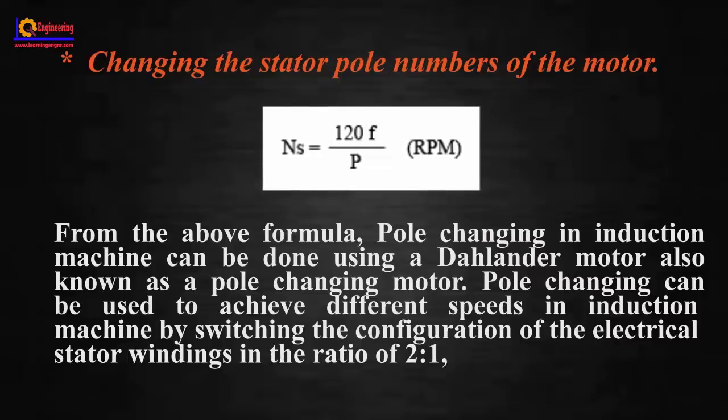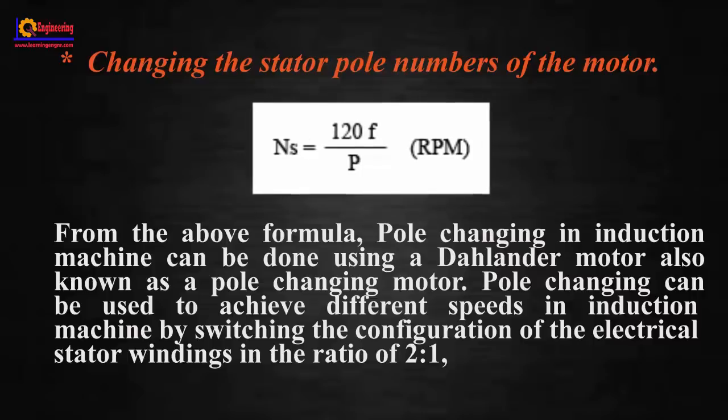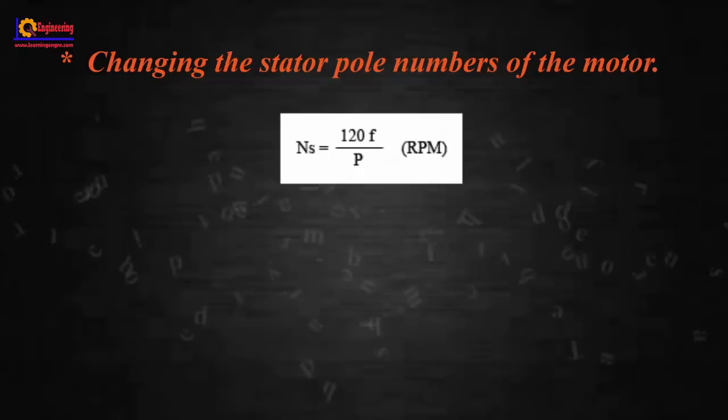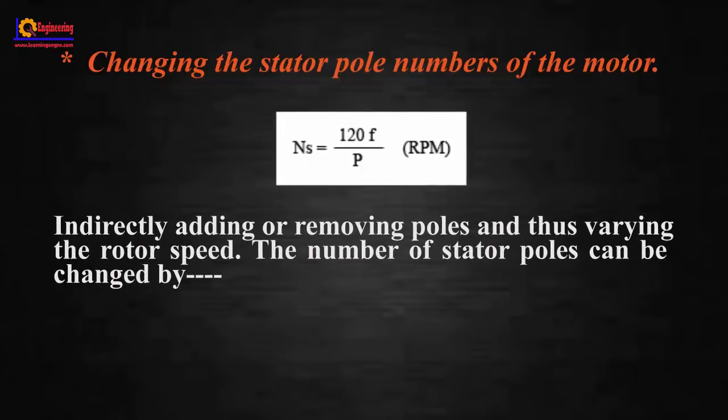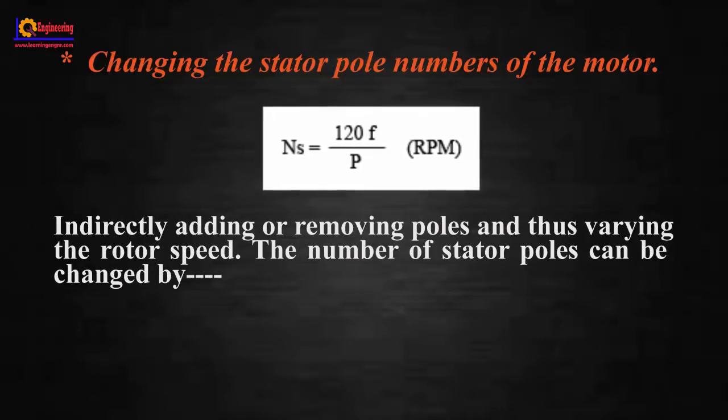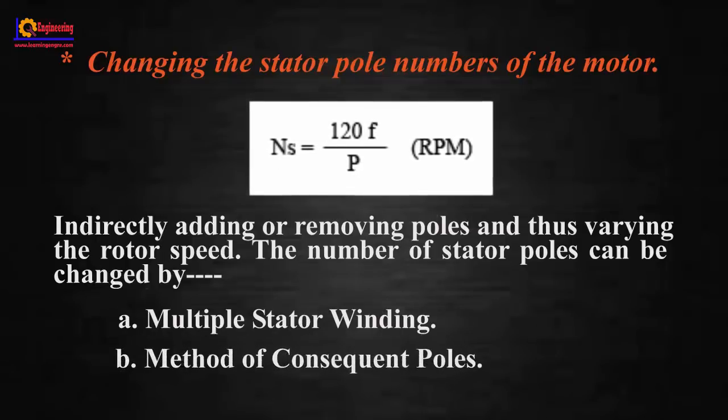Pole changing can be used to achieve different speeds in induction machine by switching the configuration of the electrical stator windings in the ratio of 2:1, indirectly adding or removing poles and thus varying the rotor speed. The number of stator poles can be changed by multiple stator winding method, consequent poles, or pole amplitude modulation.